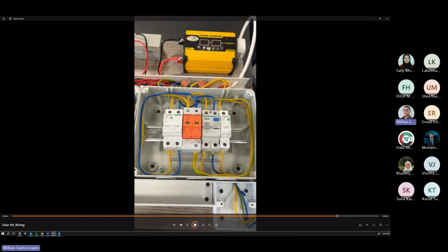The third one is the RCD, residual current device. This is to protect the user in the installation against electric shock. This component works this way: the current going in on the line is the same current going out on the neutral, so when we sum them we get zero because they are in opposite directions. The magnetic field inside is neutral.